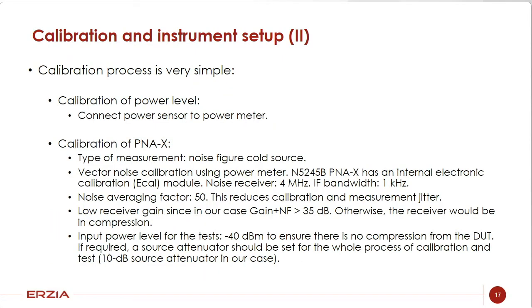The calibration process is very simple. First, you have to start by calibrating the power level. This is just connecting the power sensor to the power meter. Then you have to calibrate the PNA-X. So you have to set a lot of parameters, and we have listed here the main ones. The first one is the type of measurement. You have to select a noise figure cold source. Then we have chosen the vector noise calibration using the power meter.